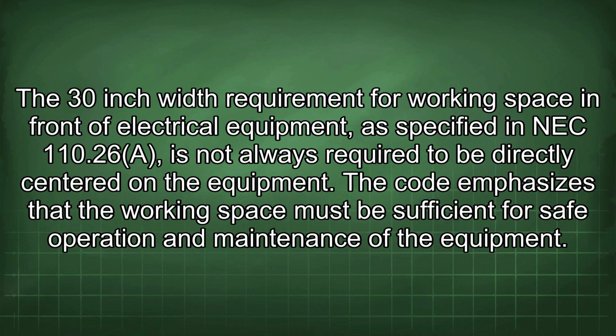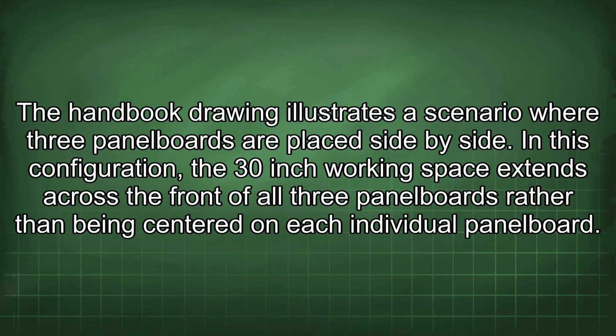The 30-inch width requirement for working space in front of electrical equipment, as specified in NEC 110.26(A), is not always required to be directly centered on the equipment. The code emphasizes that the working space must be sufficient for safe operation and maintenance of the equipment. The handbook drawing illustrates a scenario where 3 panel boards are placed side by side. In this configuration, the 30-inch working space extends across the front of all 3 panel boards rather than being centered on each individual panel board.